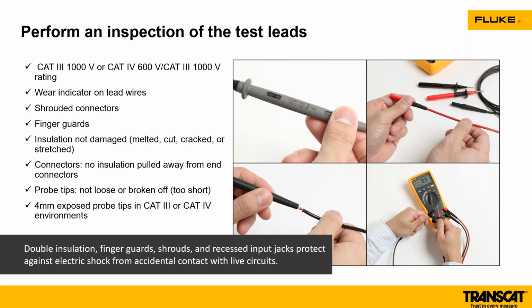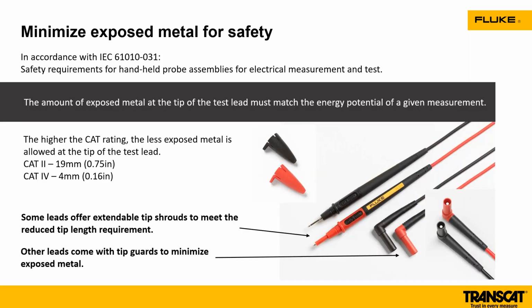Ohm them out, like in this bottom right picture. Make sure they're not breaking. You can easily do that with your meter. Now, I mentioned the exposed metal, and this is critical. Some of our test leads will either come with caps or we can twist them. The exposed metal changes the category rating of your environment.